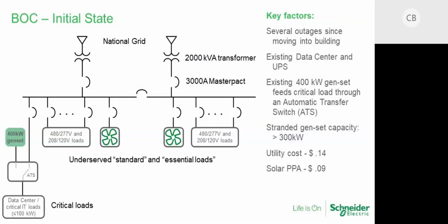So here, this shows the initial state. And on the left, you can see a 400 kW generator. It was installed solely to support the data center, and the data center had less than 100 kW load. It was designed originally and anticipated to go to 400 kW, but that load never materialized. So in effect, we've oversized the generator and we've stranded 300 kW of generator capacity that was solely dedicated to the data center.